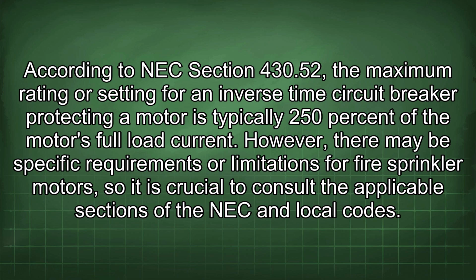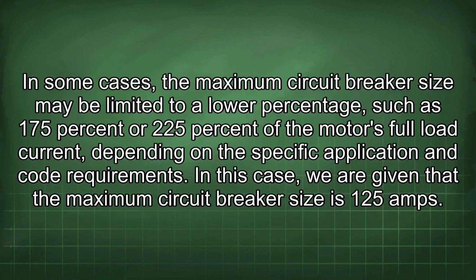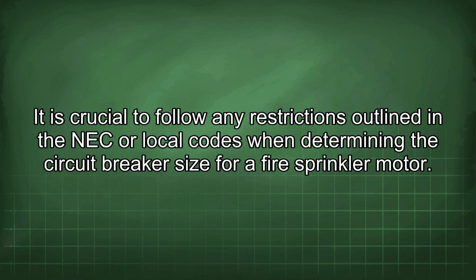motor's full load current. However, there may be specific requirements or limitations for fire sprinkler motors, so it is crucial to consult the applicable sections of the NEC and local codes. In some cases, the maximum circuit breaker size may be limited to a lower percentage, such as 175% or 225% of the motor's full load current, depending on the specific application and code requirements. In this case, we are given that the maximum circuit breaker size is 125 amps. It is crucial to follow any restrictions outlined in the NEC or local codes when determining the circuit breaker size for a fire sprinkler motor.